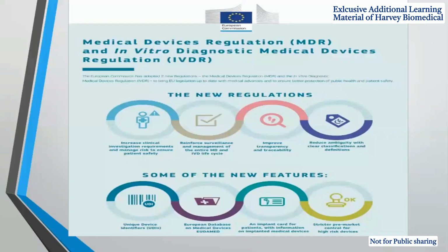Why? Because you are going to install and check the instrument, but how it enters the market and what the requirements are to enter the market, we have to be aware. Then only can we understand the complexity and criticality whenever we are changing from place to place and installation. MDD is the medical device directive, and MDR is the medical device regulations. IVDD is the in vitro diagnostic directive. IVDR is the in vitro diagnostic medical device regulations.